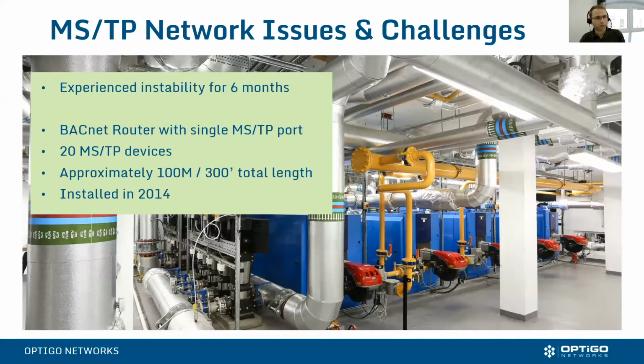Yeah, sure. We were looking to move from reactive maintenance to proactive maintenance, and to get as much data as we could from the systems we've got available. This one particular area, this boiler house, was giving us huge problems. The data was completely inconsistent, with devices online and then offline. It was completely unreliable. As we moved forward to integrating this system into CAFM software to pass on to technicians, it was unreliable. And if we couldn't rely on data from here, how could we rely on it from elsewhere? It had the potential to throw this other project into jeopardy.